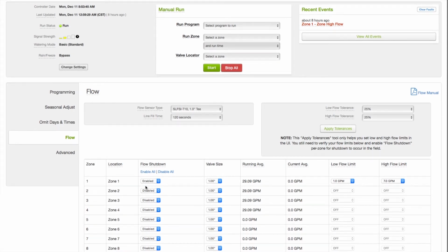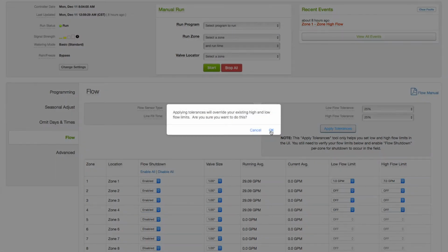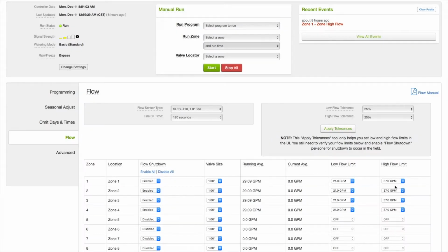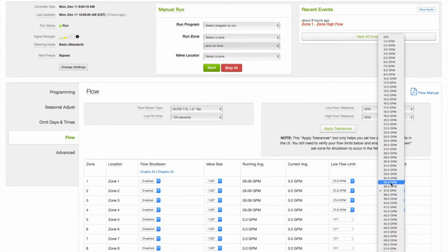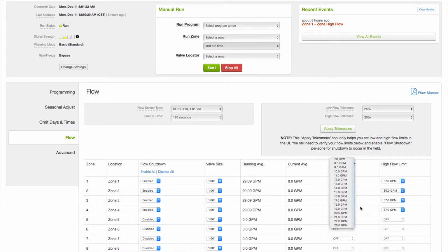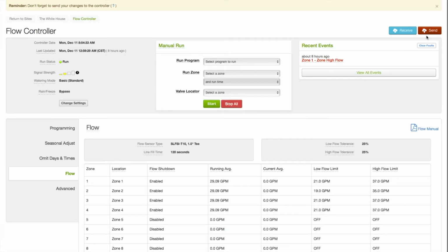So you can see this one was enabled. We'll go ahead and enable 3 and 4. Now we're going to apply the tolerances. You can see that this column now is pre-populated. So 25% under 29 gallons per minute is 21, and 25% over the 29 gallons is 37. So I can go in here, if this is not high enough or low enough, and manually set these thresholds to whatever value I would like. Save the changes and send.